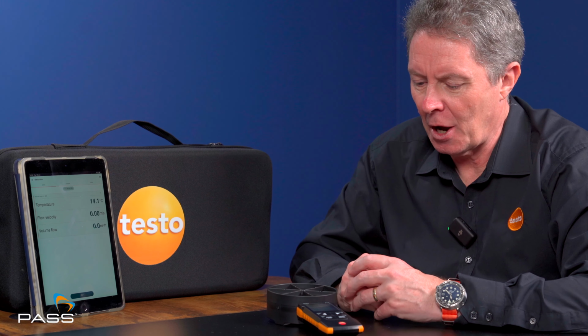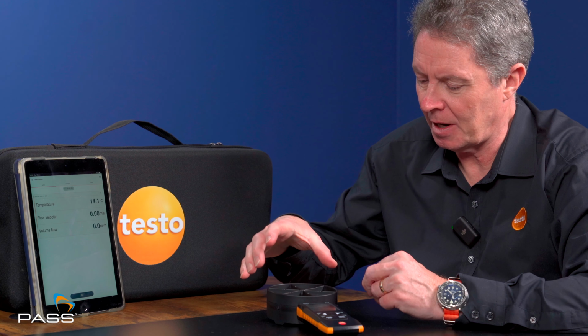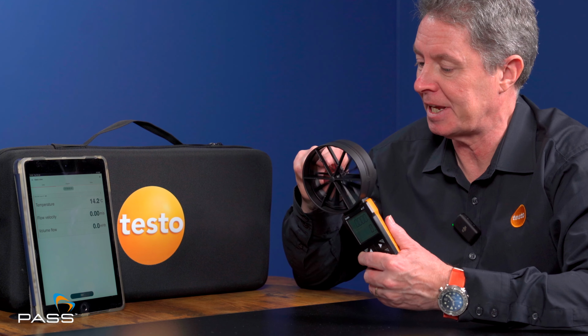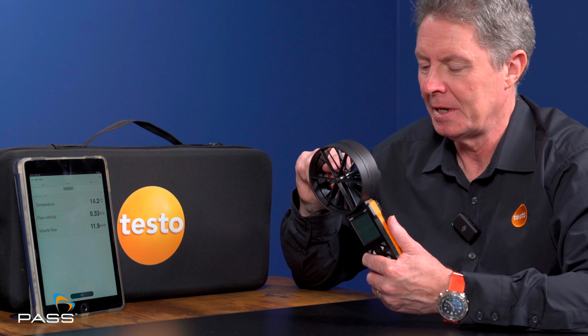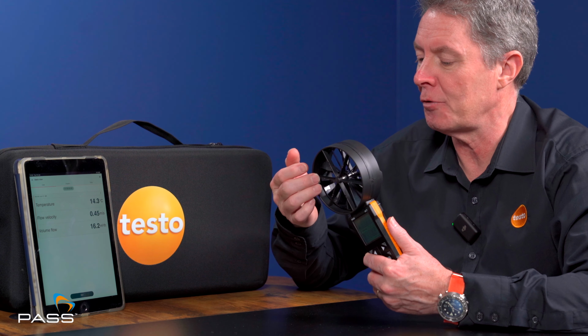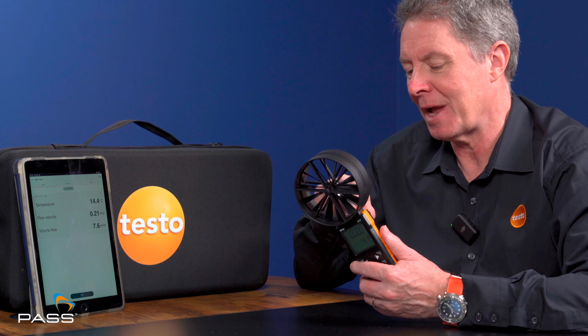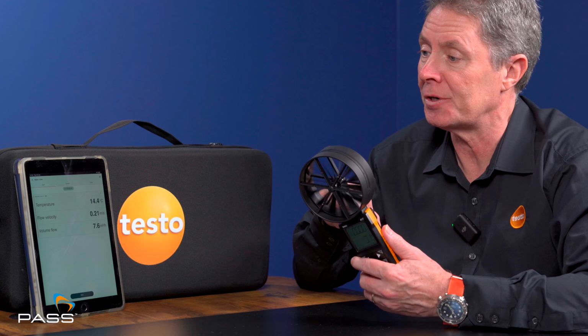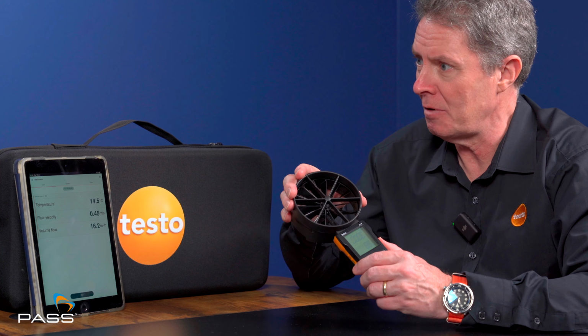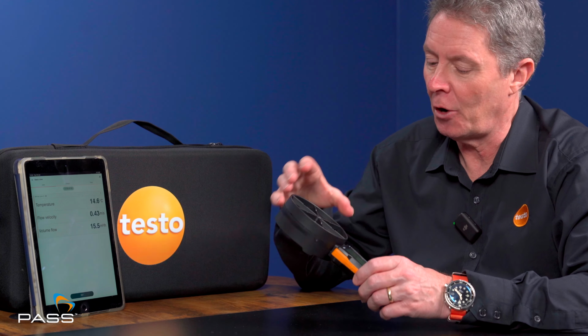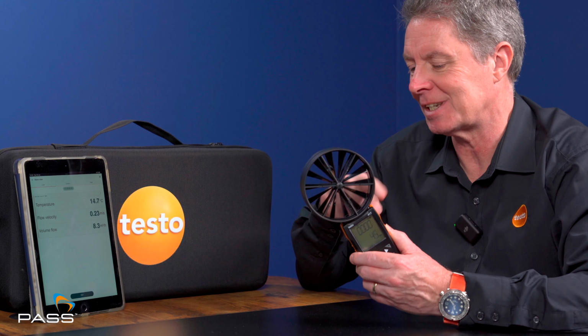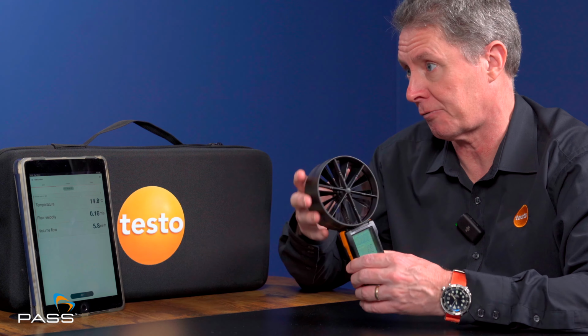So, an anemometer is a device for measuring airflow. Think of a thermometer, which is for measuring temperature. Anemometer is for airflow measurement. And this is a vane anemometer. The vane part is obviously the bits we can see here, the vanes that move around. So it's a bit like a windmill. The airflow through the vanes creates rotary motion, and then we have a sensor that is measuring that rotary motion. From that, we can then measure airflow as a velocity, so the speed going through, and also, more importantly, if we know the size of the area that's measuring, the volume of airflow that's going through as well. So an anemometer is a device for measuring airflow.